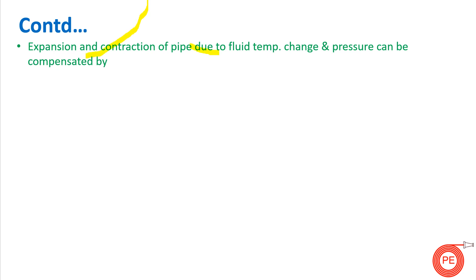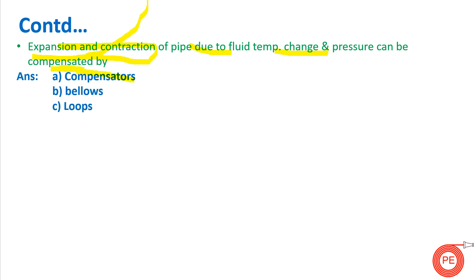The next question is: how can expansion and contraction of pipe due to fluid temperature change and pressure be compensated? It can be compensated by the use of compensators, bellows, and loops. During pipe stress analysis, these are proposed wherever there is a variation in pipe temperature due to heating or cooling, so that expansion and contraction can be minimized.